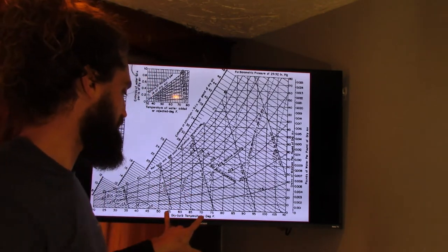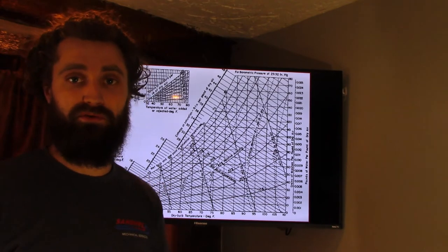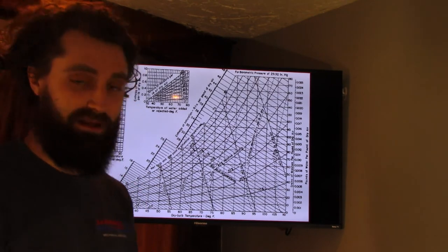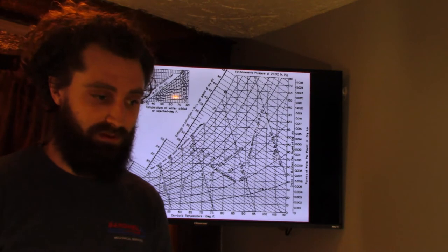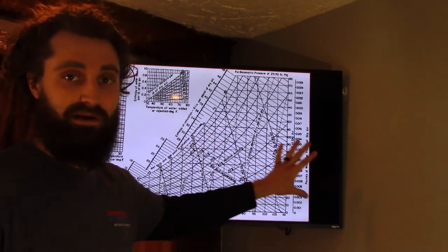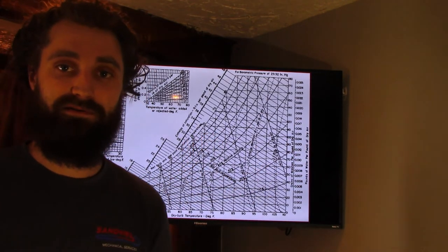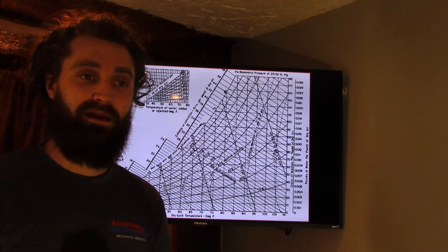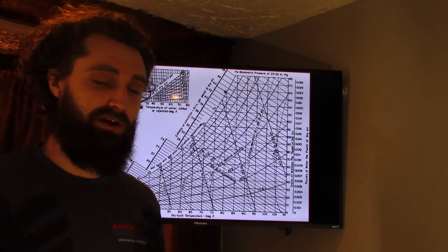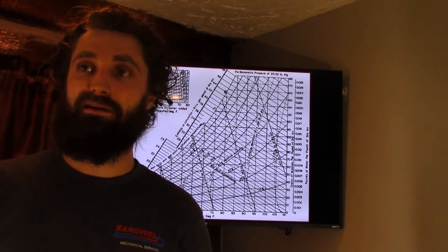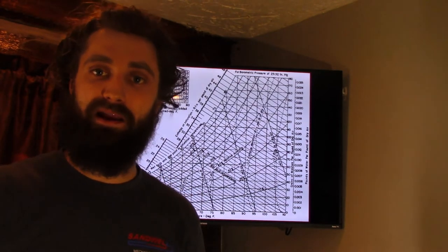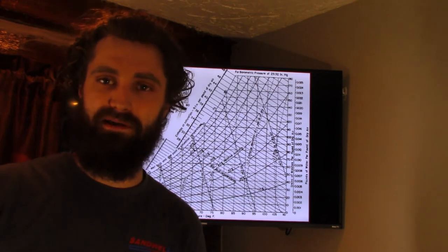So I went through with this and showed her exactly what was going on there. And in fact, it was removing a tremendous amount. I actually gave her, this thing is removing 3 gallons per hour or whatever it was. I can't even remember. But with this information, I was able to give her a hard number that your air conditioner is doing what it's supposed to do. The fact that it's humid in here probably has another cause. And it was with a site inspection. We went out and noticed that she had a cat door that was just stuck wide open, and it was just letting all this hot air in from kind of like a crawl space type of area.